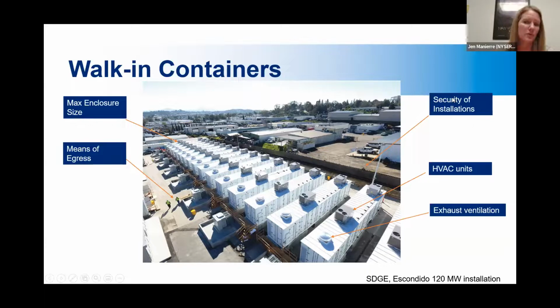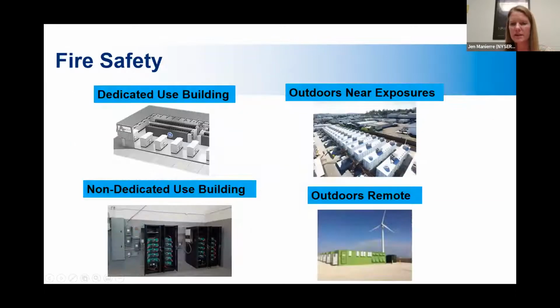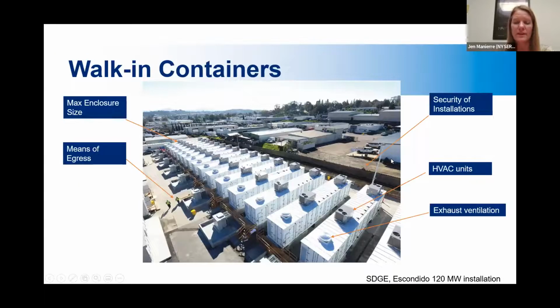Working up to the top right side of the screen, there are security requirements in the code as well, fencing, so you can see that going all around the perimeter to prevent anyone from getting near it. You can see the HVAC units on the top of the walk-in containers, making sure that they're temperature regulated and keeping those batteries happy. You can also see an example of the exhaust ventilation on them. And this is, for scale, about 120 megawatts worth of batteries here.